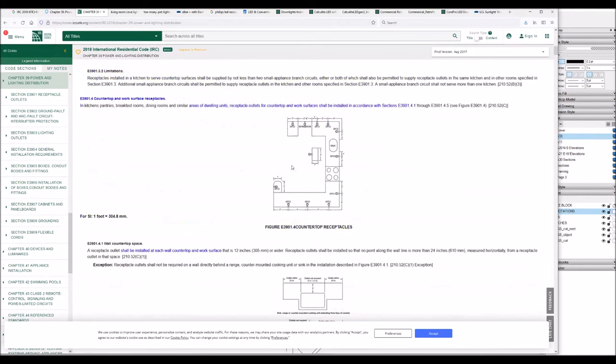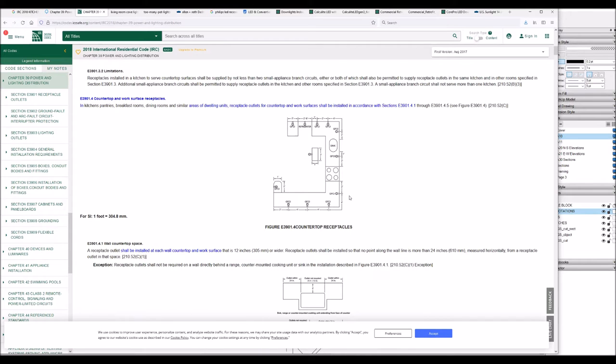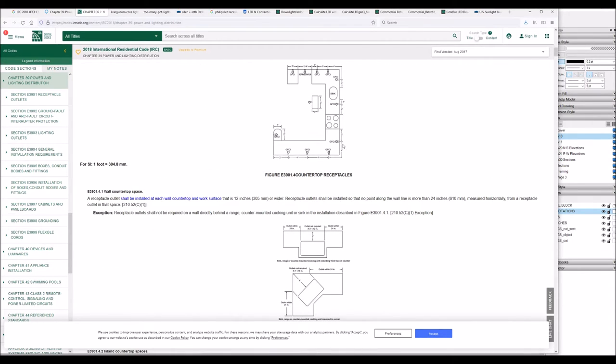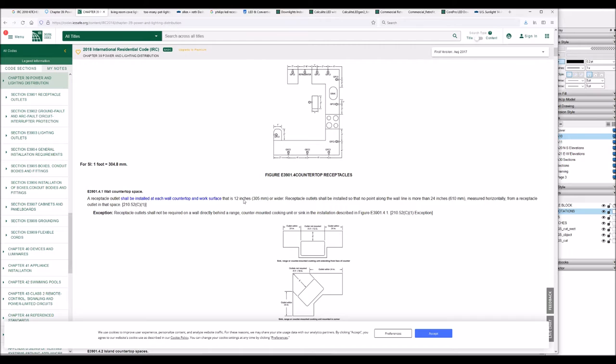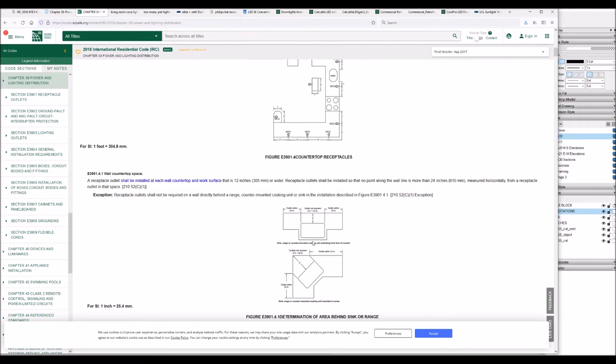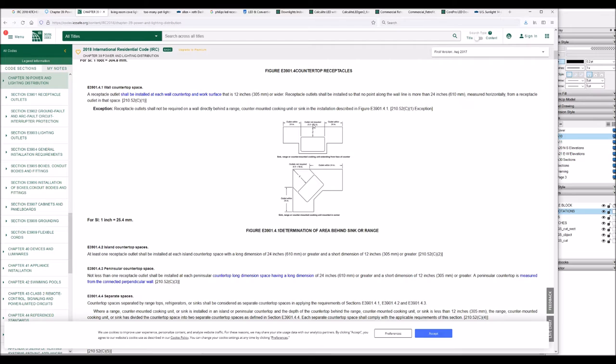When you talk about kitchens, there's a different set of rules. Basically, it comes down to four feet between plugs in simple terms. There's a whole bunch of different conditions that pop up with kitchens, so there are a variety of exceptions. For example, you don't count the space behind the stove or the space behind the sink. But any piece of countertop that is 12 inches or more wide needs to have a plug. And if you have a long stretch of counter, you can't go for more than four feet without a plug. If the space behind your sink is 12 inches or deeper, then it counts and you have to consider it when placing your plugs.